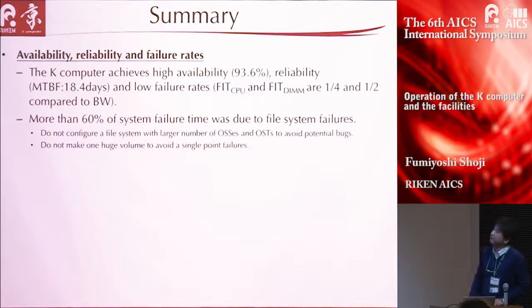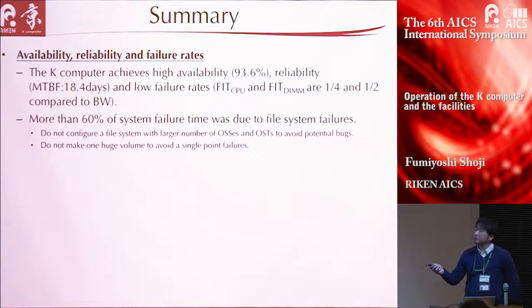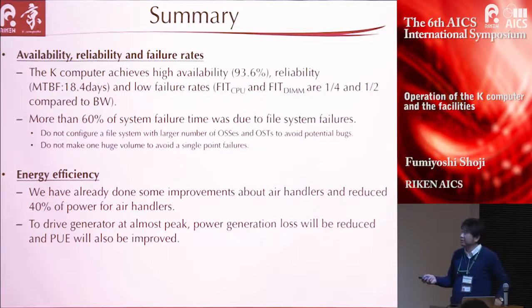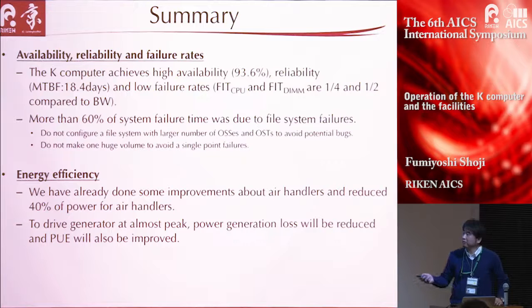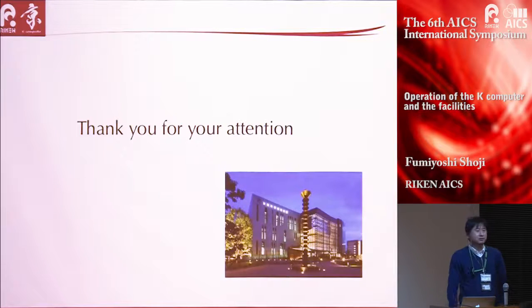Let me summarize. The K-computer achieved higher availability, reliability, and low failure rates. More than 60% of system failure time was due to file system failure. For energy efficiency, we have already done improvements to the air handlers and reduced power for air handlers by 40%. Driving the generator at near peak will reduce power generation loss and improve PUE. That's all. Thank you very much.